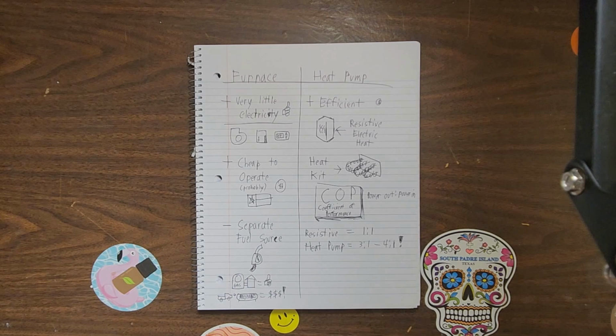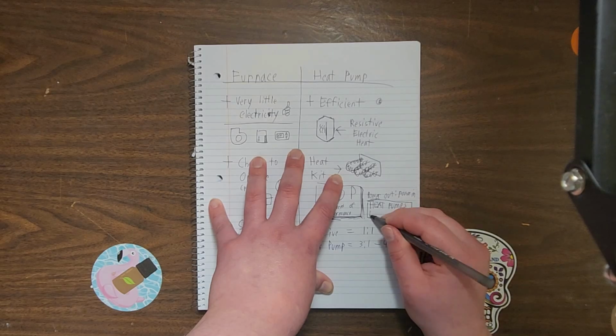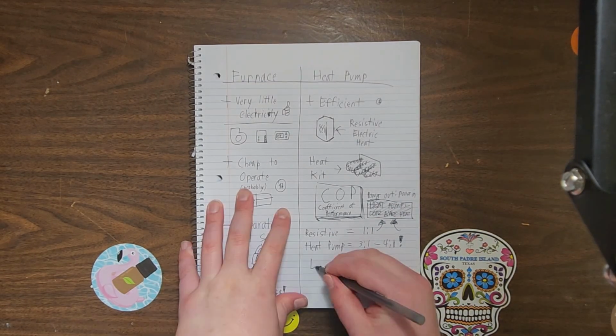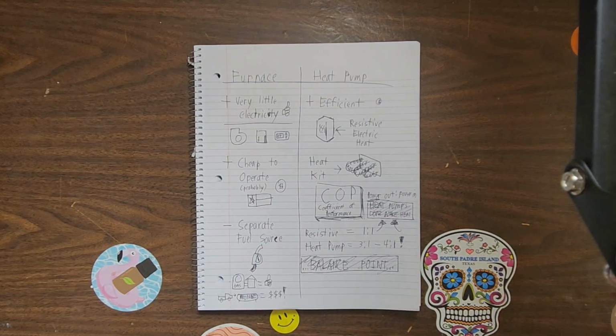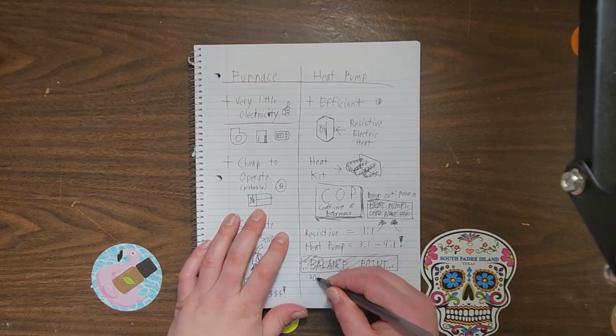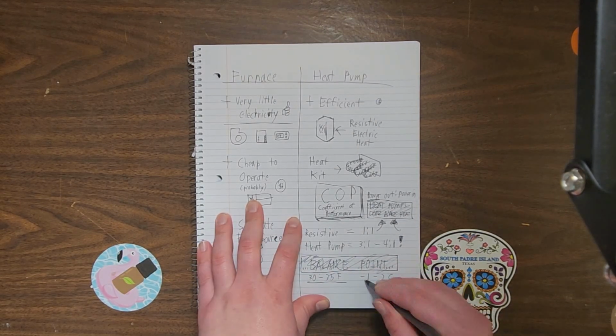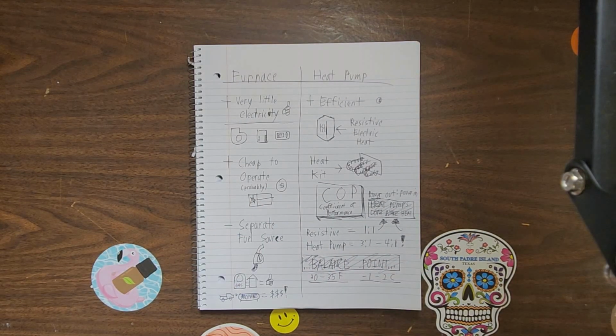Well, until you get down to a certain temperature. Since heat pumps move heat and do not create it, there's a certain point where you cannot transfer heat inside anymore. This is what's referred to as the balance point. While this will vary from system to system and is dependent on a number of different factors, generally this temperature is going to be anywhere between 30 to 35 degrees Fahrenheit. At this balance point, the heat pump cannot transfer heat anymore, and the outdoor unit begins to freeze up. This will put the system into defrost mode until the coil thaws out.